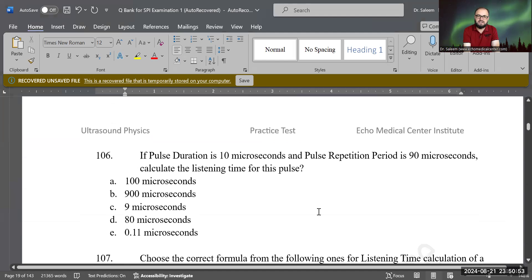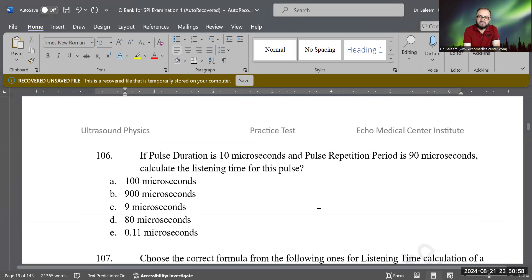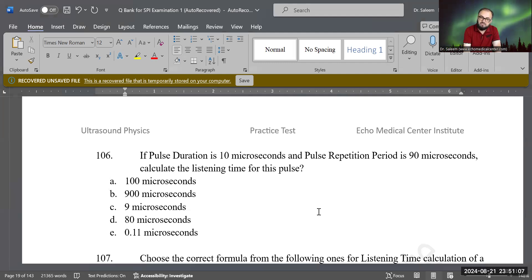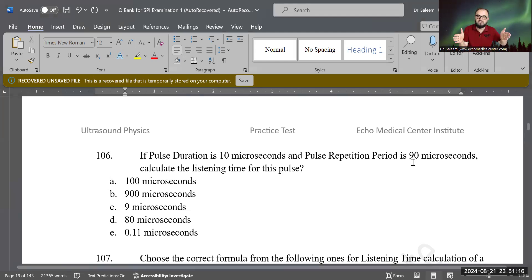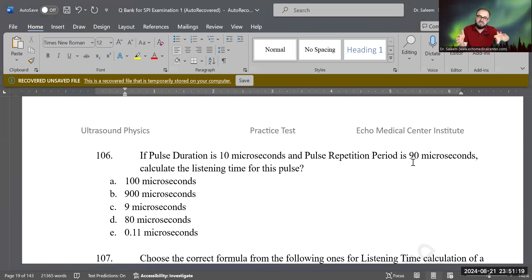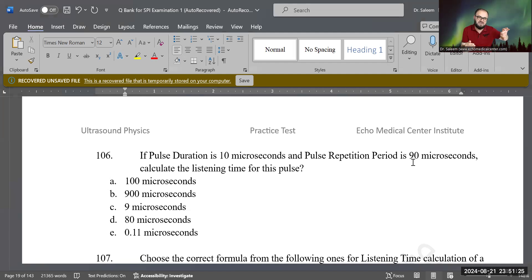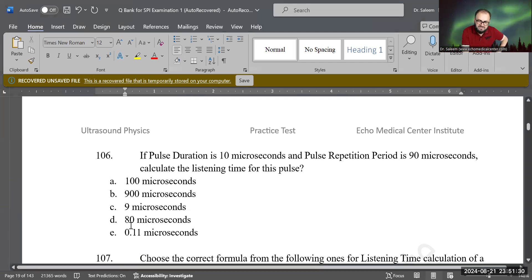Let's go to the next question. If pulse duration is 10 microseconds and pulse repetition period, PRP, is 90 microseconds, calculate the listening time. Simple and easy: if your total PRP is 90 microseconds — from the beginning of the pulse to the beginning of the next pulse — and the PD is only 10 microseconds, then the correct answer is 80 microseconds.